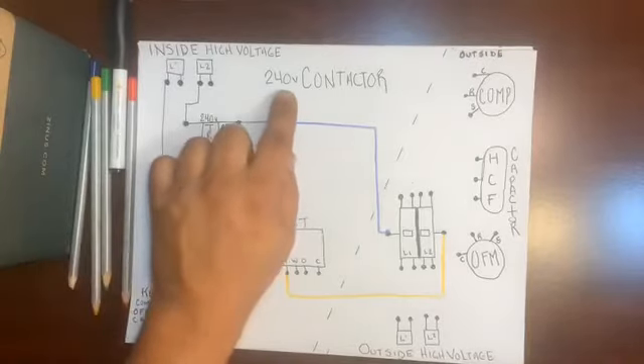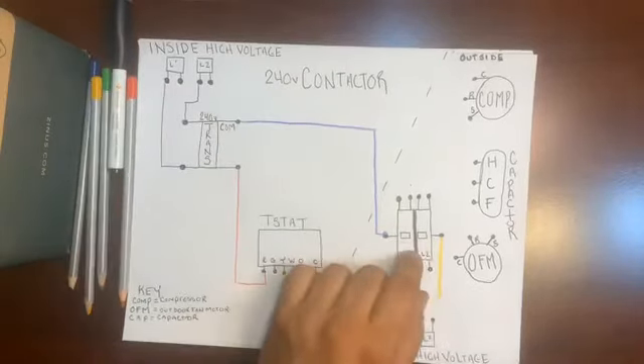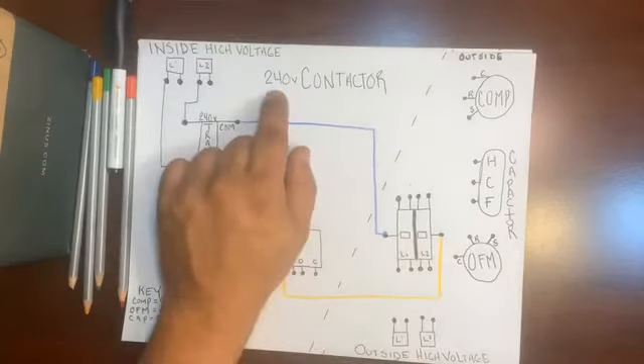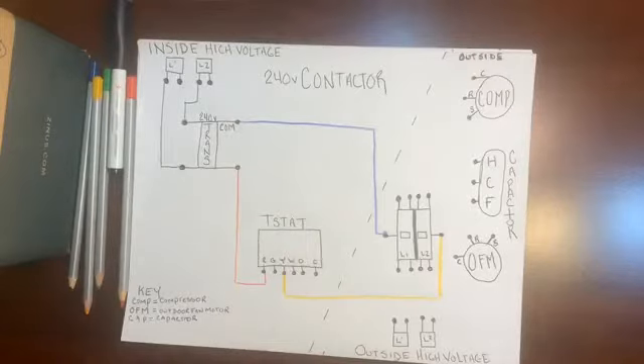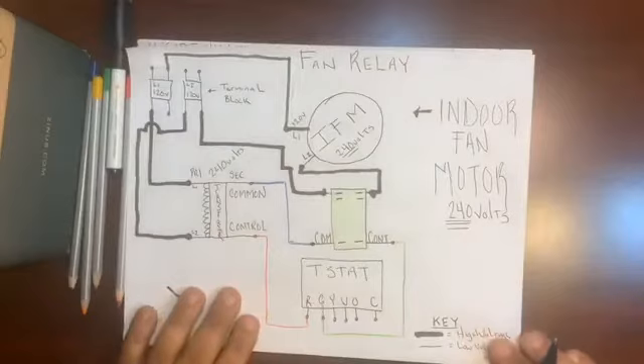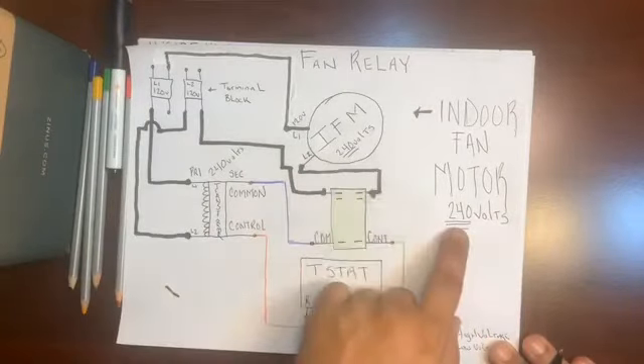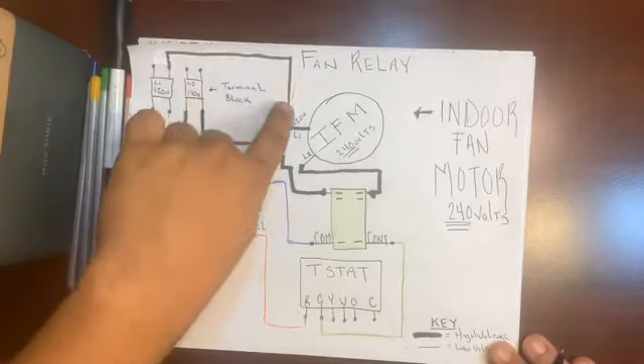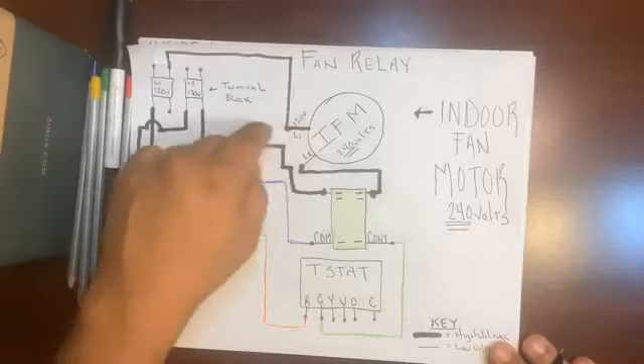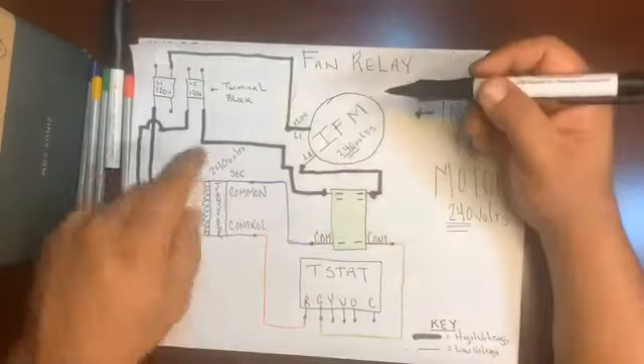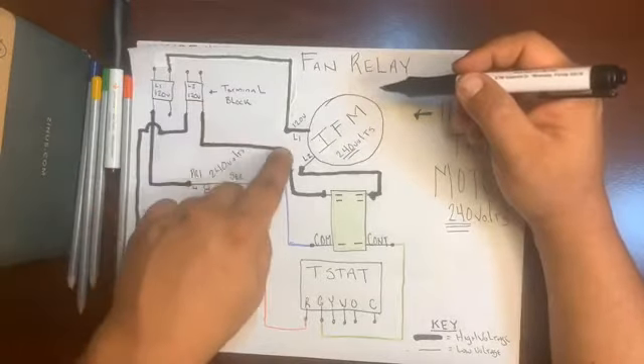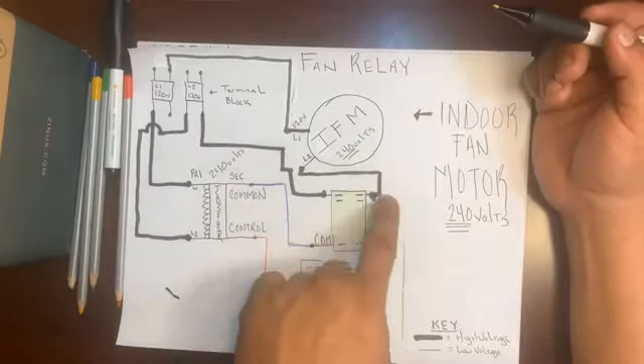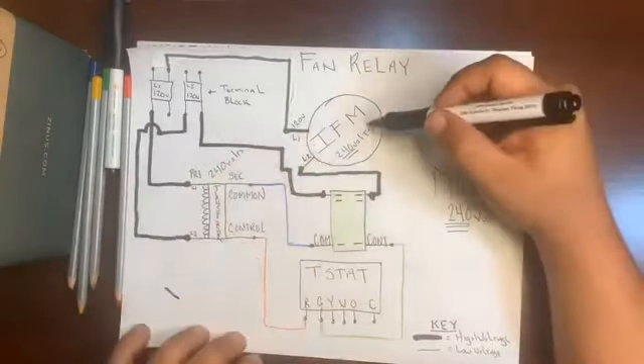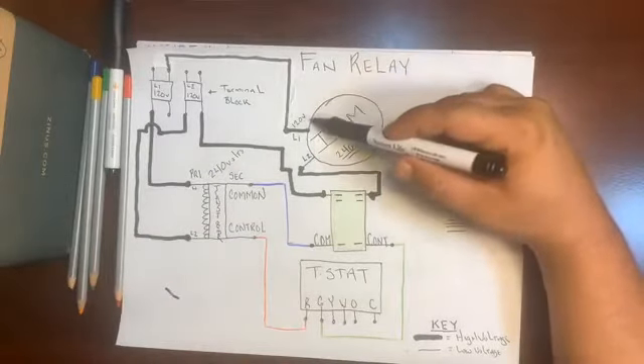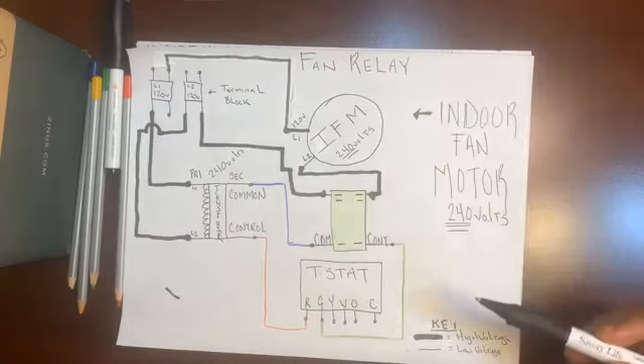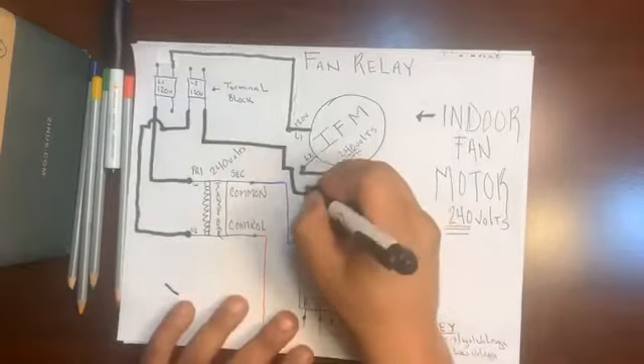When we say 240 volt contactor, what we mean is that this relay is one of the only relays that's going to receive a full 240 volts. Because when we look back at our previous lesson, we had our indoor fan motor, which needed 240 volts. We had a high voltage common feeding the indoor fan motor, one leg, high voltage common in the hand at all times, just like the low side. And then the other 120 volts for the fan motor was being directed down in through the fan relay, and then turning on the fan motor by completing the 240 volts, because this fan motor will not move unless it has all 240. It can have a constant 120 on common and not turn on. But when we look at this, we see how we're splitting only 120 volts.